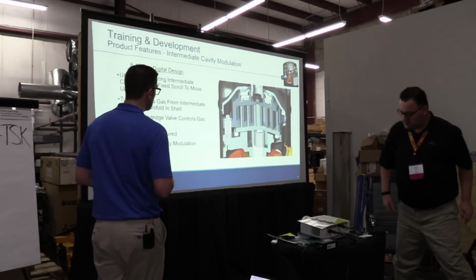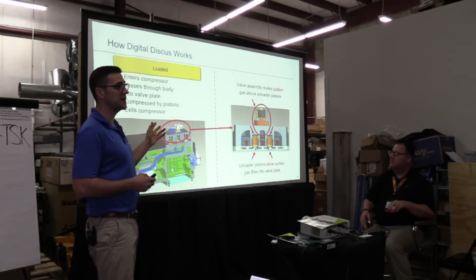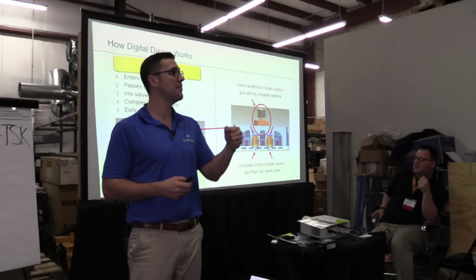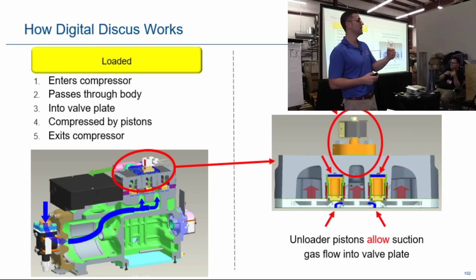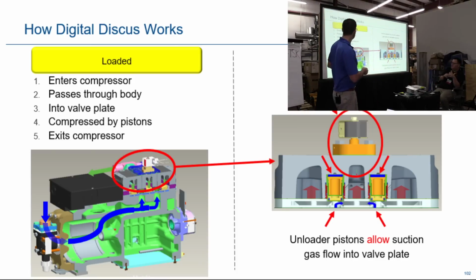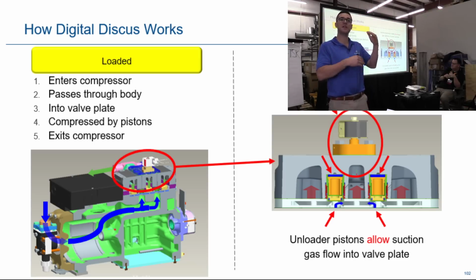Digital Discus works on the same principle. They have a solenoid on top of the Discus compressor, for example. When it's loaded up, the unloader pistons allow suction gas to flow through. When the solenoid activates, it pushes down some pistons and blocks them, so there's no work being done. And it's all done on time again, too.